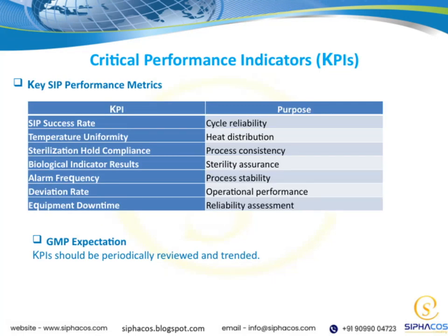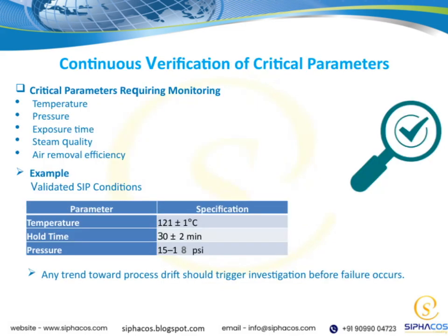When it comes to good manufacturing practices, we expect key performance indicators, or KPIs, to be reviewed regularly and tracked over time. This helps us spot trends and catch issues early. Some critical KPIs include the SIP success rate, which tells us about cycle reliability, and temperature uniformity, showing how well heat is distributed. We also monitor sterilization hold compliance for consistent processes, biological indicator results to assure sterility, alarm frequency for stability, deviation rates for operational performance, and equipment downtime as a measure of reliability. These metrics keep everything on track. When we see any sign of process drift, it's a signal to pause and investigate before things go wrong.